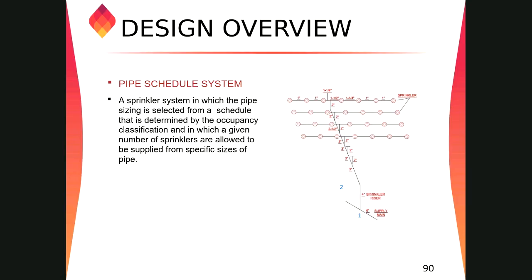Yeah, clear. So any change in direction or diameter of the pipe, we will consider that point as a node. Suppose this is a sprinkler we are taking in the hydraulic area. This is node 1, right? And this sprinkler is node 2.